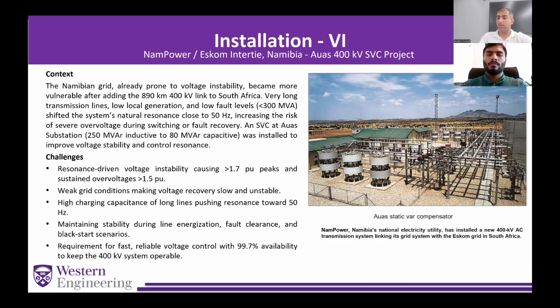Namibia's 400 kilovolt link to South Africa spans 890 kilometers, loading the grid with line-charging capacitance and low fault levels that nudged resonance towards 50 hertz. As we all know, frequency is very important. The results were dangerous overvoltages. Peaks were above 1.7 per unit, and it sustained levels above 1.5 per unit during switching and recovering. So keeping the intertie reliable required fast damping, black start readiness, and near constant availability. As you can see in the picture, the substation and the SVC installed in the real world.